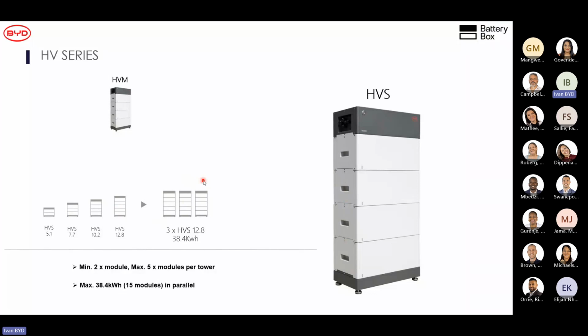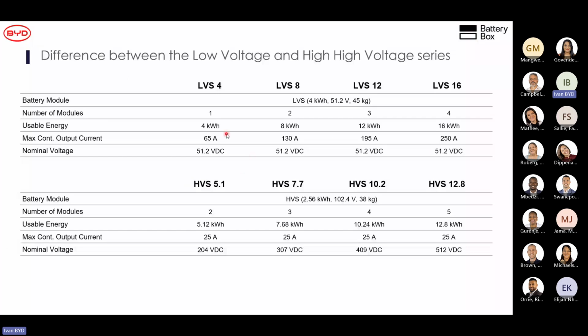Here's some of the differences between high voltage and low voltage batteries. This is common to a lot of high voltage and low voltage batteries, where here we can see the nominal voltage of your low voltage battery stays the same, but your maximum output current goes up. Whereas on your high voltage batteries, as you add modules, your maximum output current stays the same, but your voltage goes up. You also have to keep an eye that the inverter that you're connected to can work with the voltages that the batteries are set to. So you have to make sure that the operating voltage of your battery bank is within the operating voltage of your inverter.